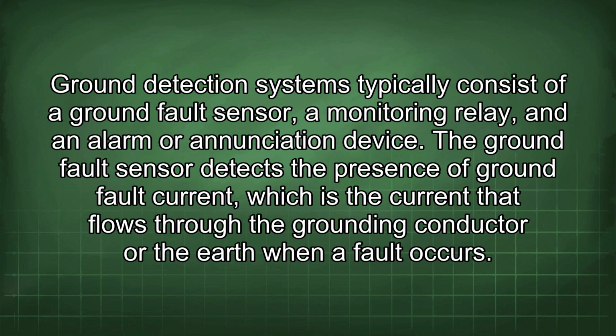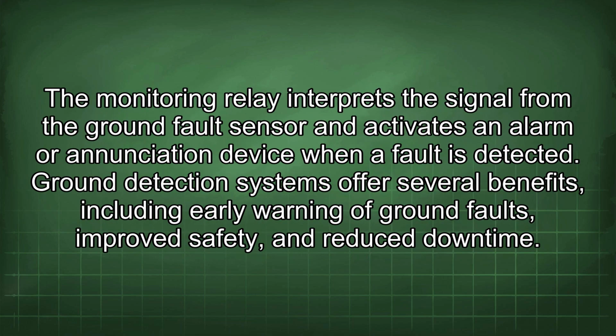Ground detection systems typically consist of a ground fault sensor, a monitoring relay, and an alarm or annunciation device. The ground fault sensor detects the presence of ground fault current, which is the current that flows through the grounding conductor or the earth when a fault occurs. The monitoring relay interprets the signal from the ground fault sensor and activates an alarm or annunciation device when a fault is detected. Ground detection systems offer several benefits, including early warning of ground faults, improved safety, and reduced downtime.